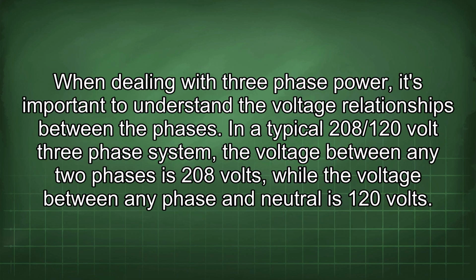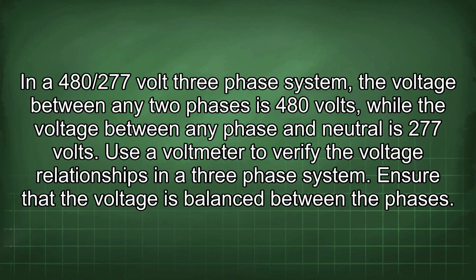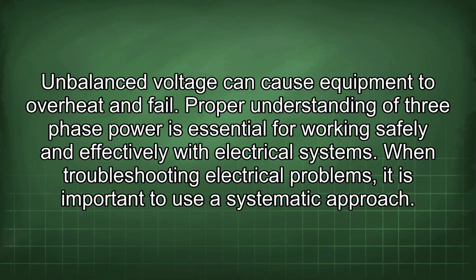When dealing with three-phase power, it's important to understand the voltage relationships between the phases. In a typical 208/120 volt three-phase system, the voltage between any two phases is 208 volts, while the voltage between any phase and neutral is 120 volts. In a 480/277 volt three-phase system, the voltage between any two phases is 480 volts, while the voltage between any phase and neutral is 277 volts. Use a voltmeter to verify the voltage relationships in a three-phase system. Ensure that the voltage is balanced between the phases. Unbalanced voltage can cause equipment to overheat and fail. Proper understanding of three-phase power is essential for working safely and effectively with electrical systems.